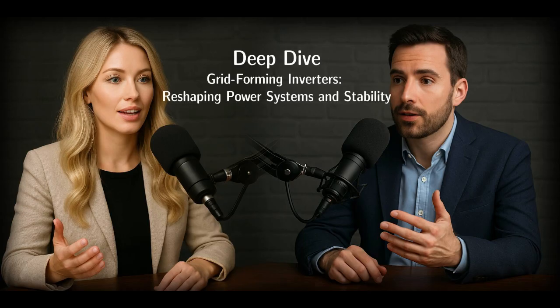Okay, so the challenges are clear. What solutions are being put in place? What's happening on the hardware and system side? Well, on the inverter side, manufacturers are building in more sophisticated fault response capabilities, like programmable fault current levels and temporary current boosting specifically to help protection operate. There's also a big push for better communication integration, allowing inverters and protection relays to coordinate in real time. And standards like IEEE and IEC are evolving to define expected fault behavior more clearly.